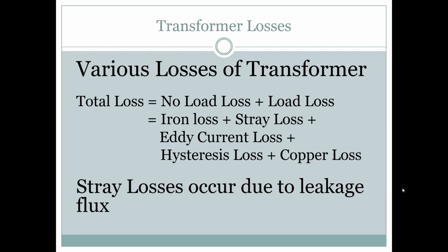Then comes the load loss. Load loss can be divided into stray losses, because wherever the junction points are, there will be some leakage losses continuously close to the circuit. And hysteresis loss, the BH curve. In ideal condition, that BH curve should be followed continuously. Whenever you switch on the transformer, when electromagnetic induction is taking place, that BH loop will start forming. So it has to follow the same path, but it actually does not. Some BH loop is getting created and consuming losses. That is your hysteresis loss. The hysteresis loop is formed in the BH curve.